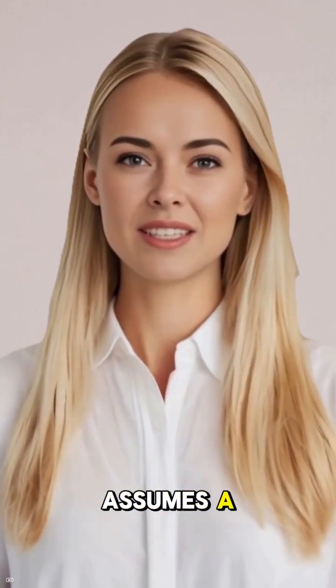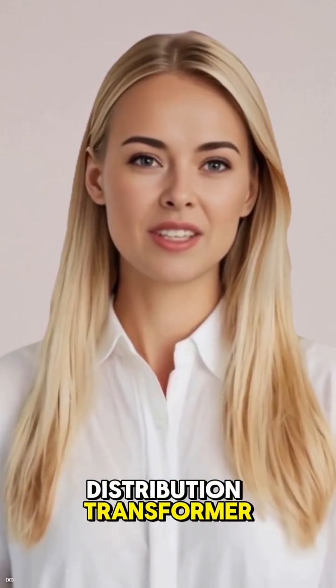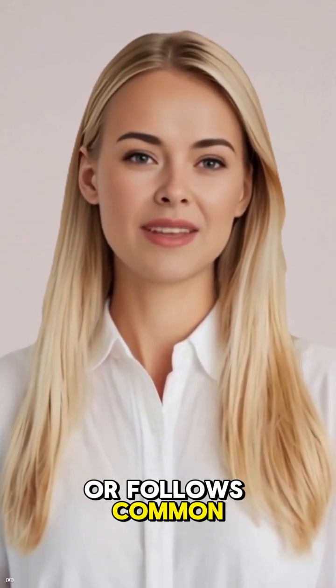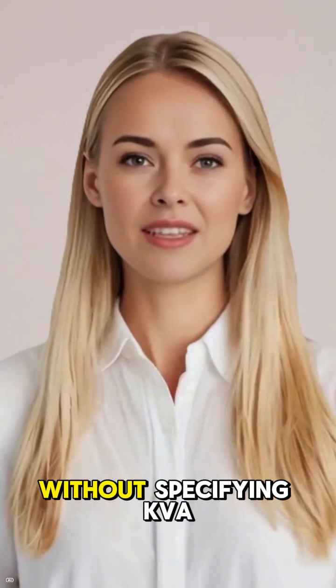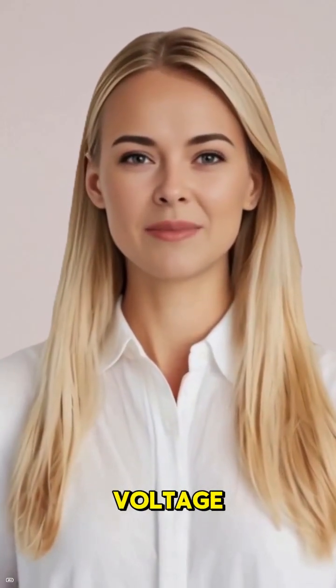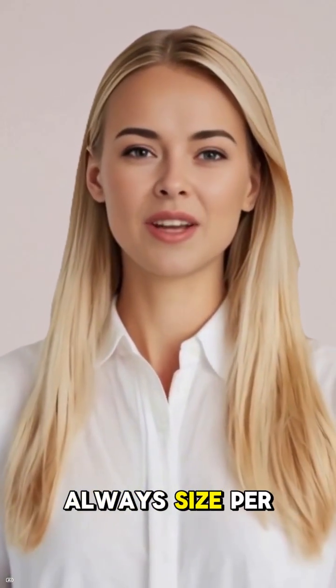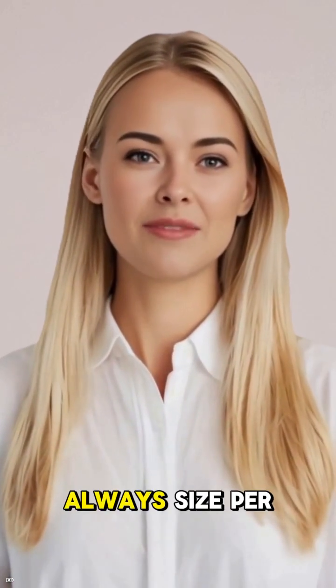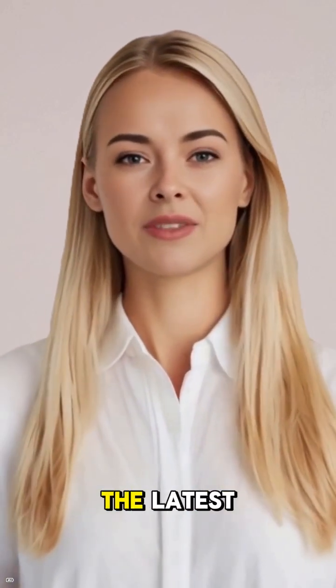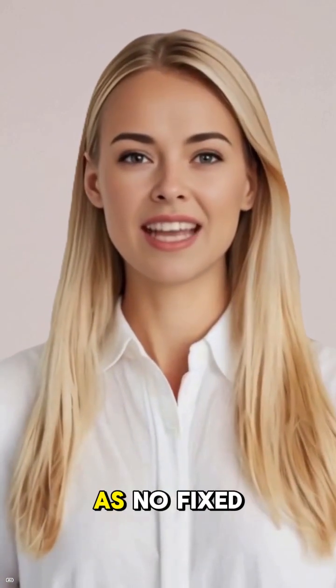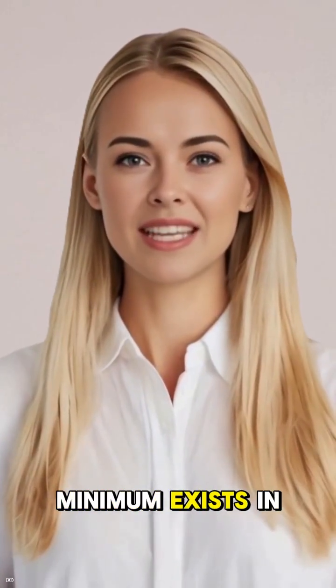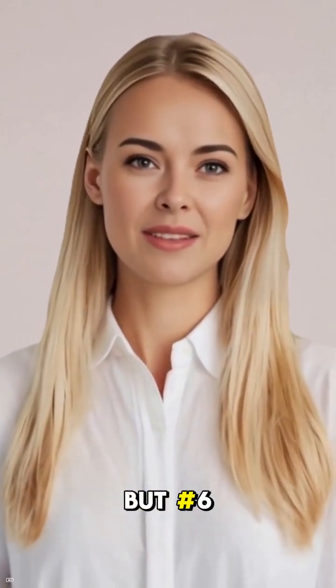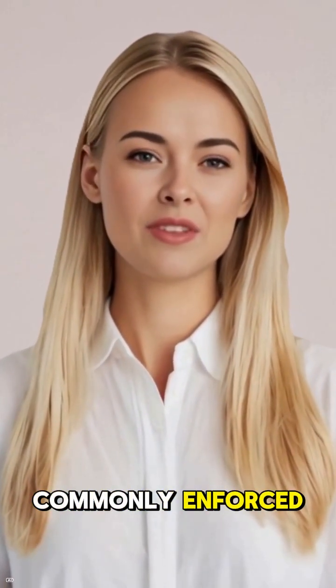If the question assumes a typical dry-type distribution transformer, even small kVA, or follows common exam phrasing for minimum size without specifying kVA or voltage, number 6 is the expected choice. Always size per actual rated current times 1.25 and verify with the latest OESC edition, as no fixed one-size-fits-all minimum exists in the literal code text, but number 6 is the safe, commonly enforced floor for copper.